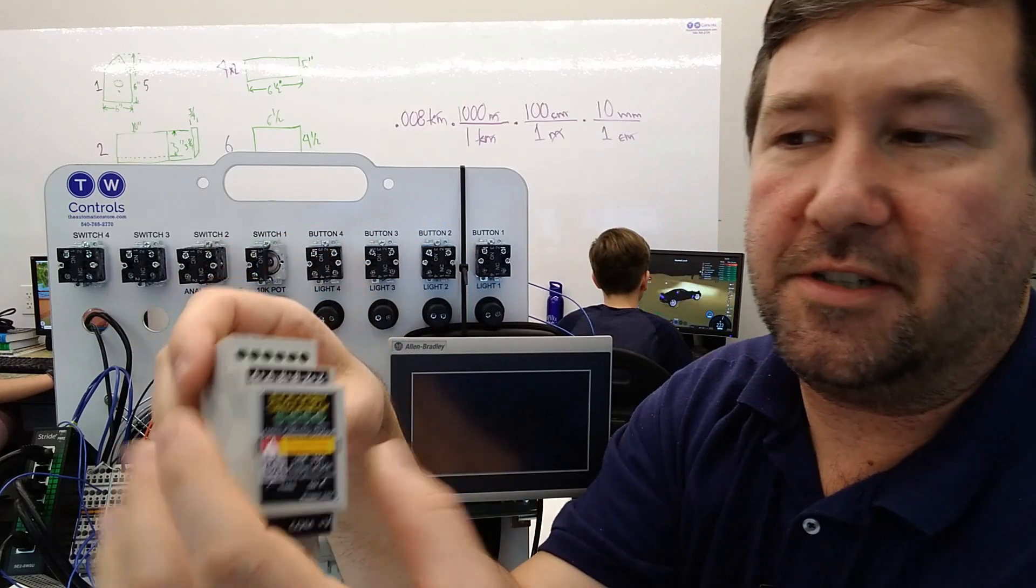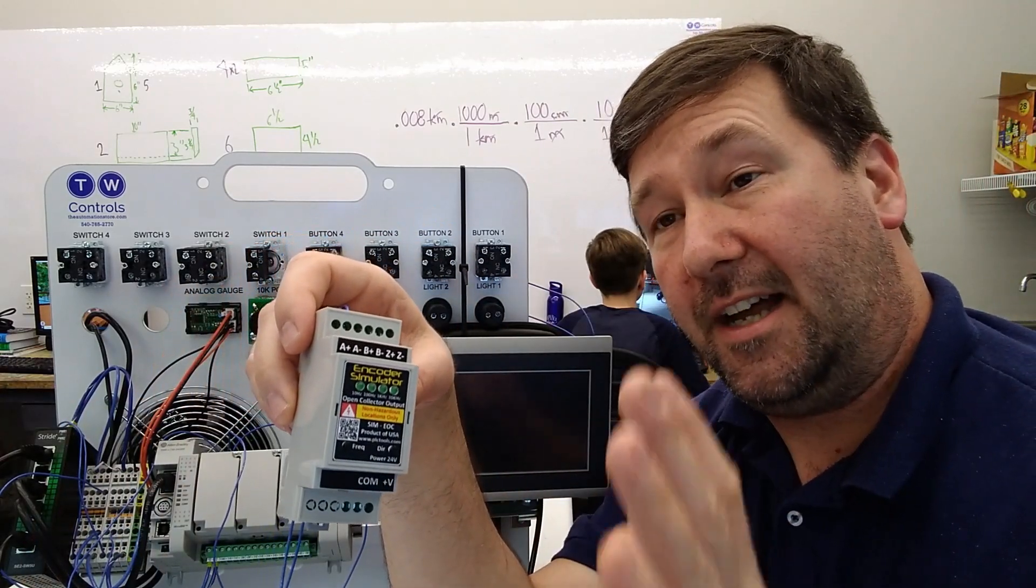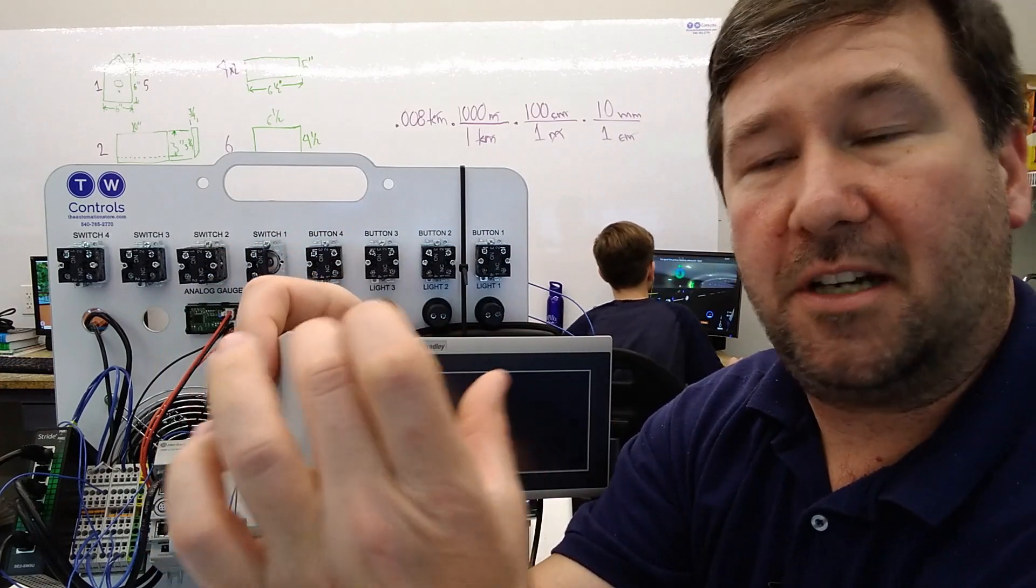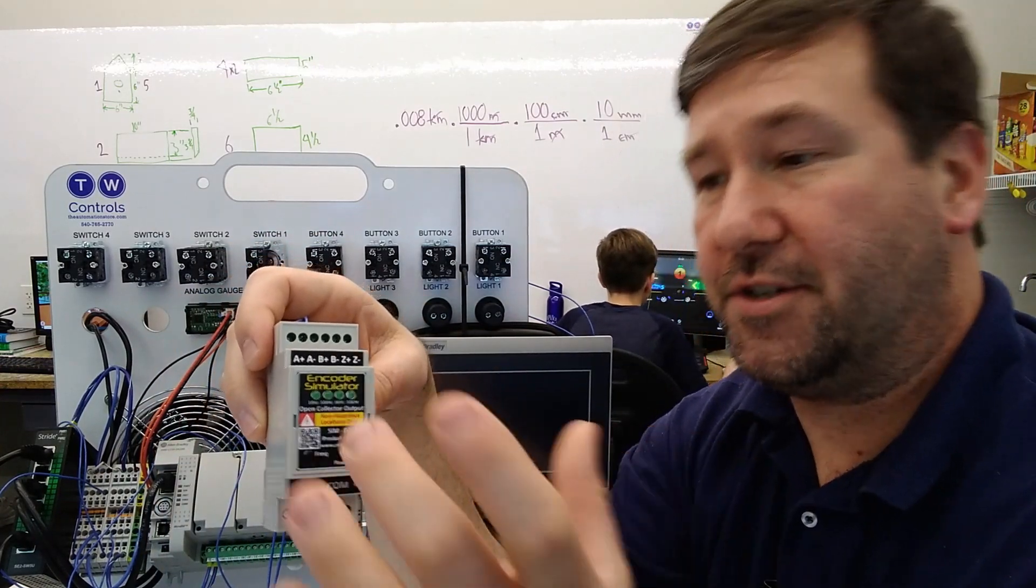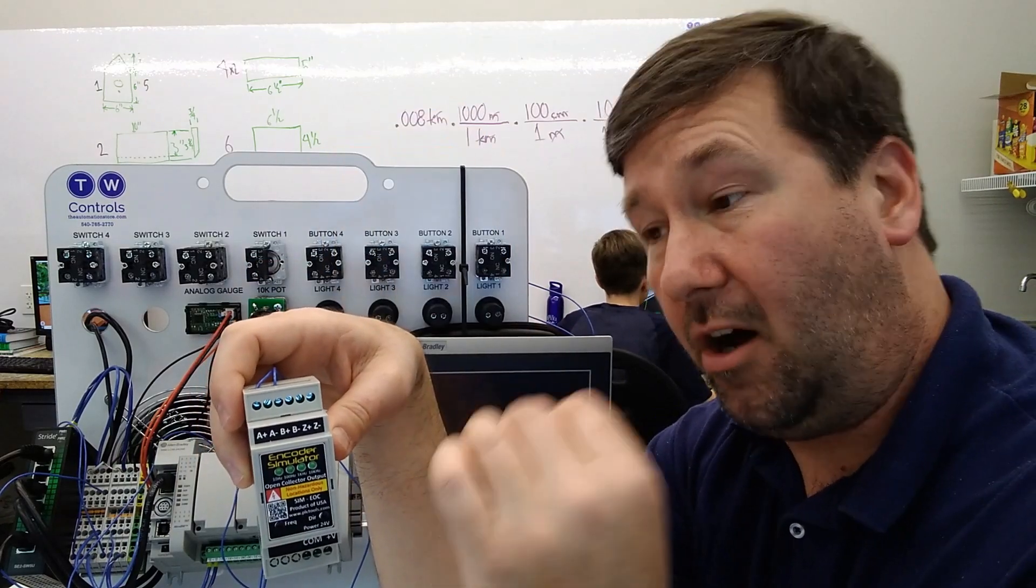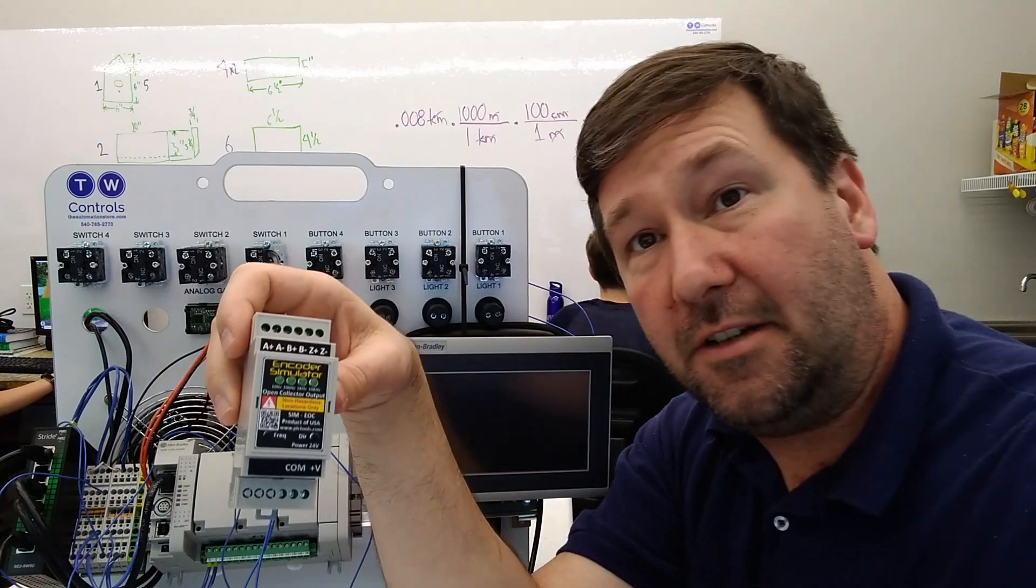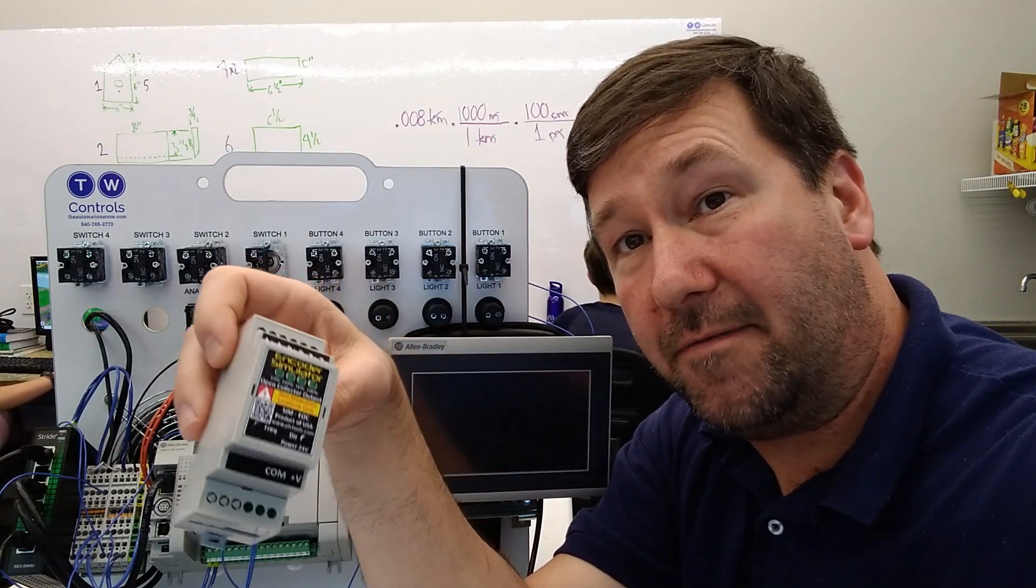Now this is a little confusing because you see the plus and minus, and you think you have to make it a circuit, but it's not. What it is, is these are always going to be opposite, and it's a checking feature. When A plus is on, A minus is going to be off. And when A plus is off, A minus is going to be on. So you only need to use the plus when you're connecting to the micro 850.